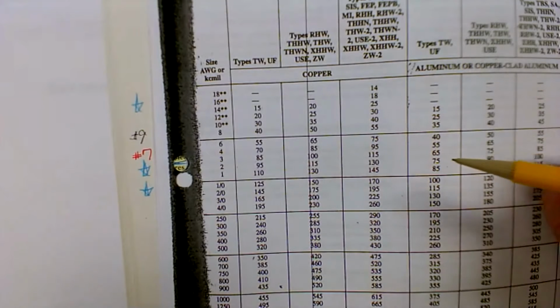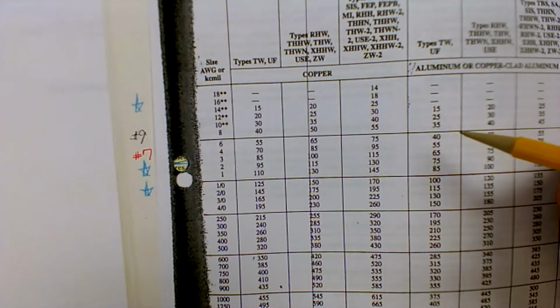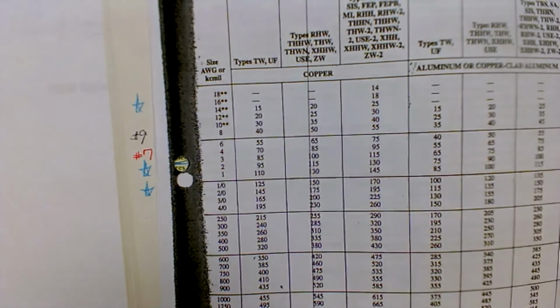We're typically running these wires in 1-inch conduit. Right. So in 1-inch conduit, there's a limit to how many wires you can put in there. If it's PVC conduit, there's actually a rating. Yeah. I can show you how to go online and look at the National Electrical Code for free, and I can show you where the table is. It's in the back of the code book, in Table 9, Chapter 9, where the tables are.